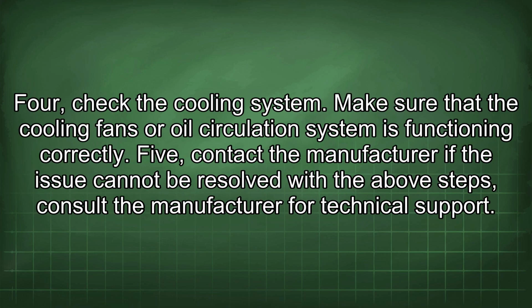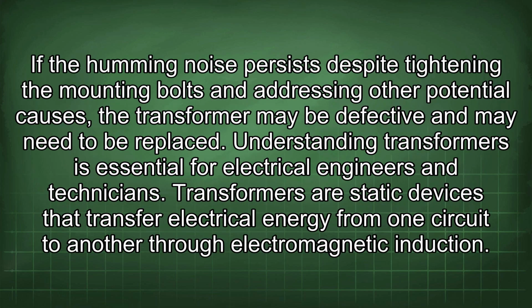4. Check the cooling system. Make sure that the cooling fans or oil circulation system is functioning correctly. 5. Contact the manufacturer. If the issue cannot be resolved with the above steps, consult the manufacturer for technical support. If the humming noise persists despite tightening the mounting bolts and addressing other potential causes, the transformer may be defective and may need to be replaced.